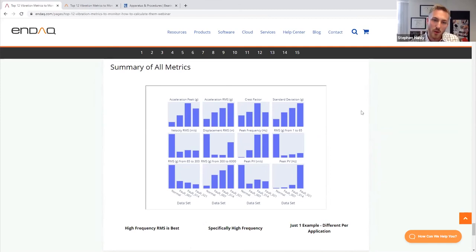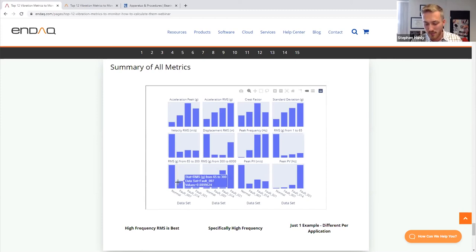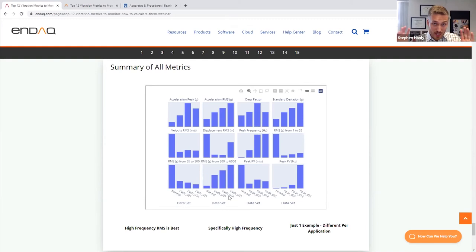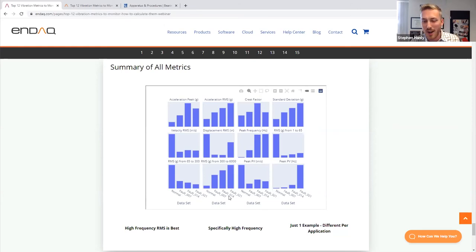Here's a summary of all the metrics. We started by looking at overall RMS, which showed a good trend, but an even greater trend occurs when we look at just the high-frequency content, because the normal bearing had a lot of RMS energy that was misleading and not really indicative of damage. For this particular application, the high-frequency RMS is what corresponds most to damage. I'd encourage you to start with all these metrics, play around with different frequency ranges using the PSD, and pick the frequency range and the RMS within that range to track. You'll need to do some exploration first to identify which frequency range matters most for your application.